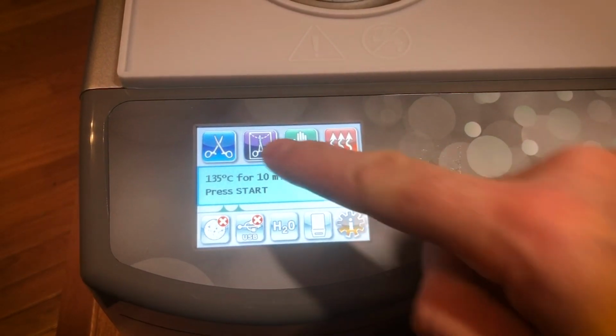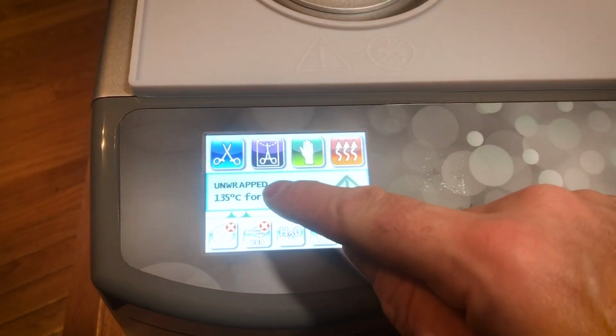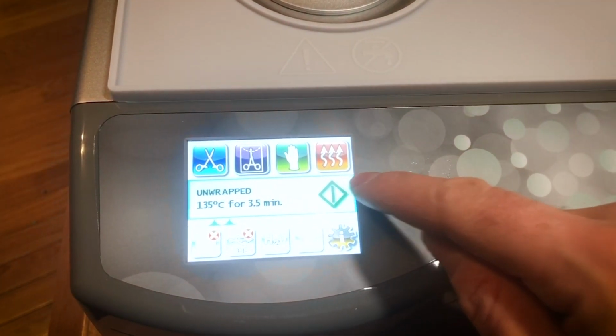And once it's snugly in place, it'll click in, and then we go to choosing which cycle we're going to do. Since we're going to be turning out a lot of instruments and using them pretty soon after sterilizing them, the quickest and most efficient way of doing this is choosing the cycle that is unwrapped. After about 6 minutes of running time, it is time to unload the cassette out of the autoclave, and that's just simply done by pulling it out.